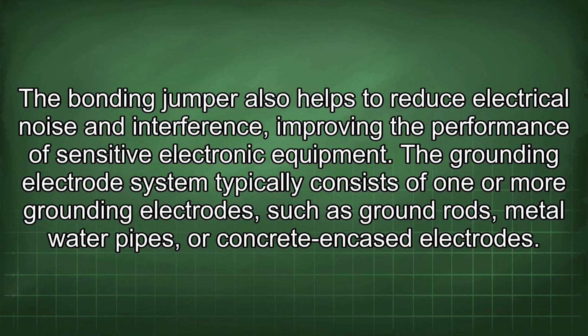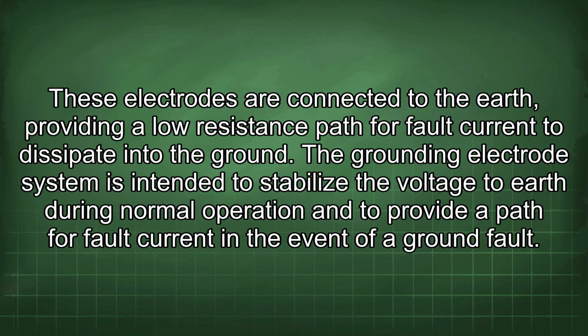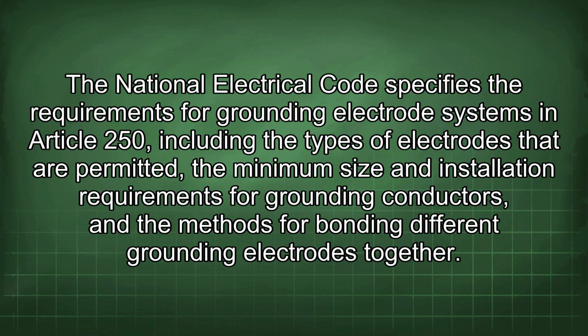The grounding electrode system typically consists of one or more grounding electrodes, such as ground rods, metal water pipes, or concrete encased electrodes. These electrodes are connected to the earth, providing a low resistance path for fault current to dissipate into the ground. The grounding electrode system is intended to stabilize the voltage to earth during normal operation and to provide a path for fault current in the event of a ground fault. The National Electrical Code specifies the requirements for grounding electrode systems in Article 250, including the types of electrodes that are permitted, the minimum size and installation requirements for grounding conductors, and the methods for bonding different grounding electrodes together.